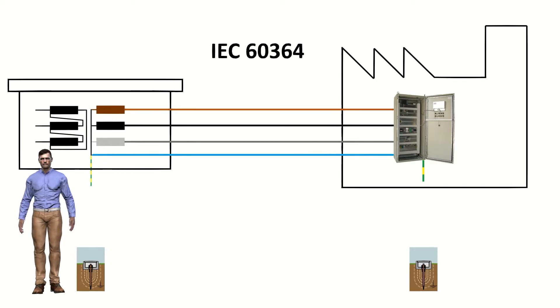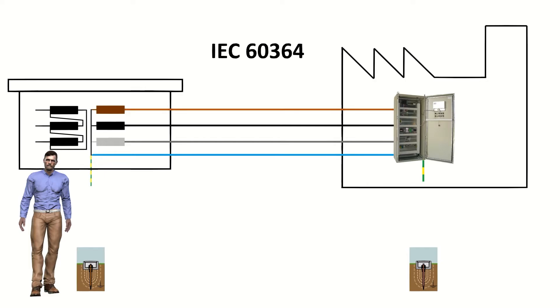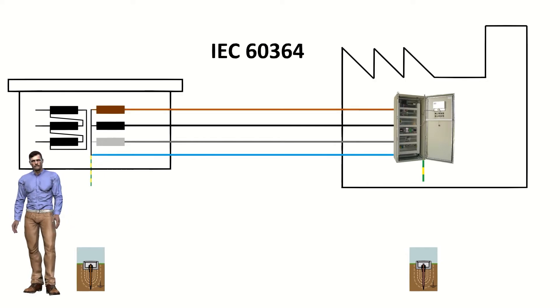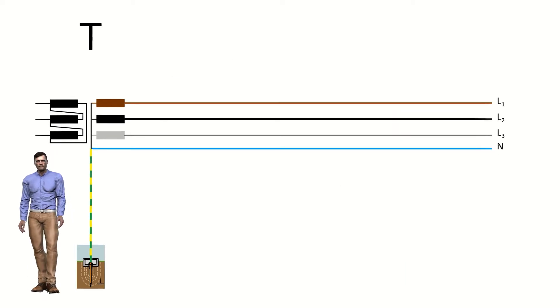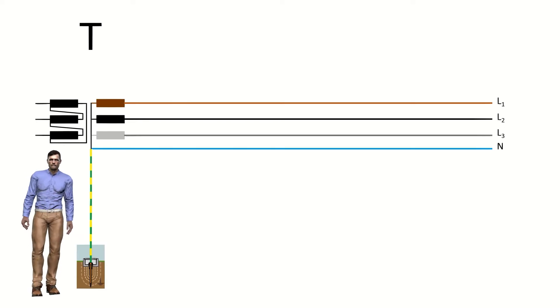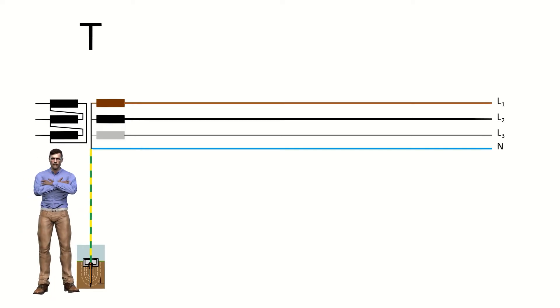We can name the different distribution schemes using a multi-letter system. The first letter is associated with the type of earth connection of the network, normally in the transformer of the transformation center, although it can also be complemented in other points. The second letter is associated with the type of connection of the masses of the loads such as electrical machines. For the first letter, we use the letter T if there is a direct connection to earth in the transformation center, normally the neutral tap of the transformer.